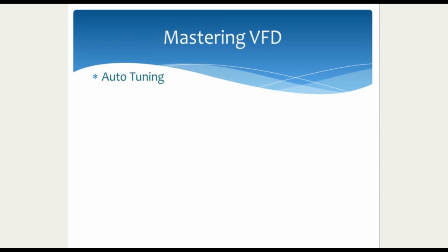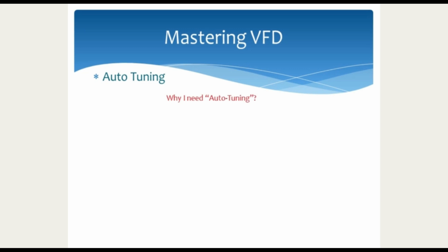Auto-tuning. The question comes, why do I need auto-tuning? The answer to that is some VFD functions require tuning before being selected. Now, what could be the example of those functions? So we have auto torque boost and vector control. There might be other functions as well, but these in my experience are often required.